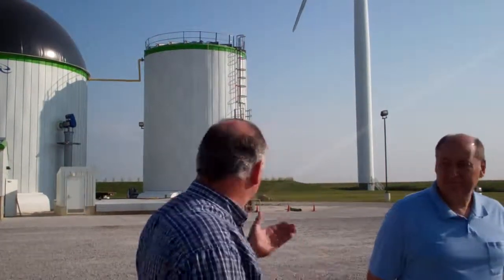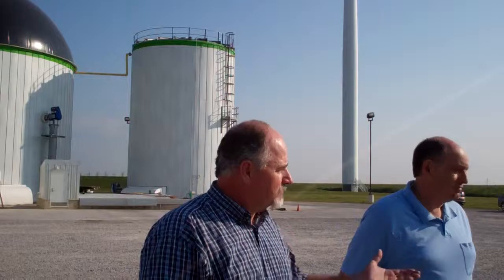Tank on the right, your COD, chemical oxygen demand, is one of the tests we do. That tells us, basically, it's kind of like a calorie count or the potential food power that's in that product. We'll maintain about a 200 to 250,000 COD in the acid-producing tank. After we put it into the digester, I think the digestion process is designed for about, what, a 29-day? 21. We actually have our product in here 40 to 50 days. You can tell that just by, you've got a 750,000 gallon tank, we're putting in 21,000 gallons a day. So it's just basic math.